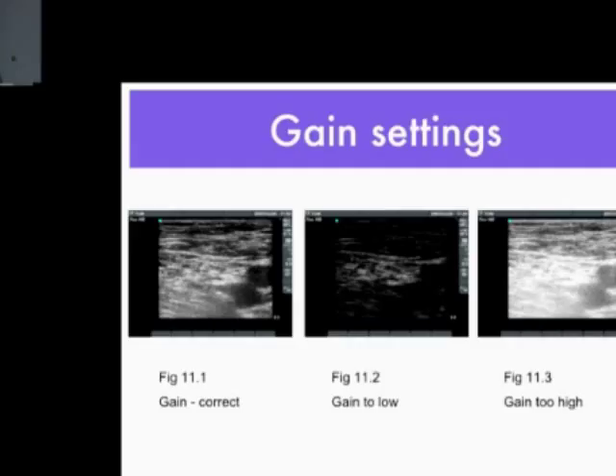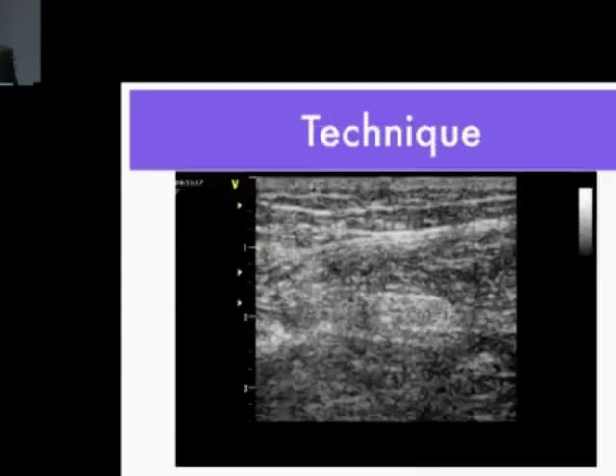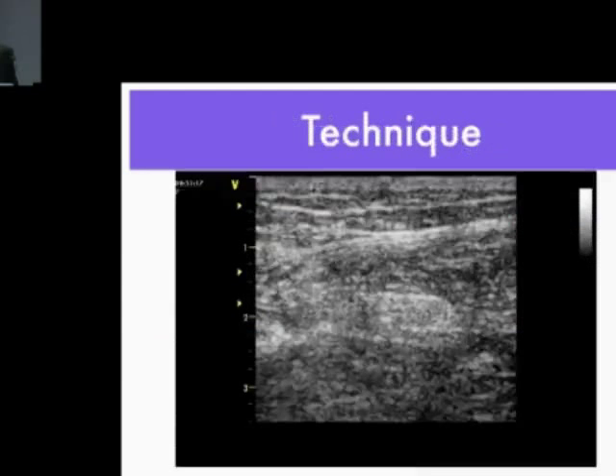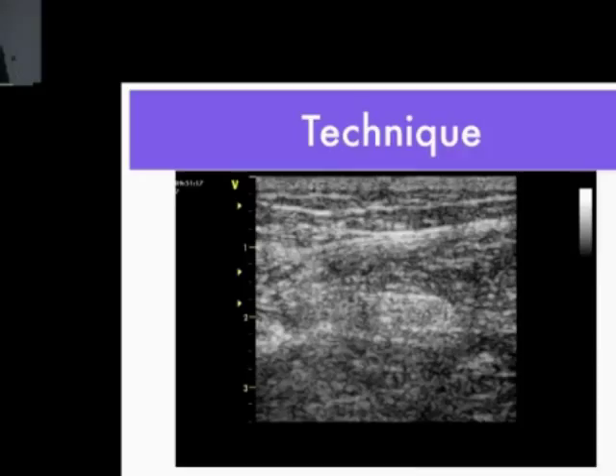Gain has individual preferences, but we must pay attention to it. One of the most important things related to gain is reducing the intensity of ambient light — experienced echocardiographers always reduce ambient light to get less reflection and less tendency to turn the gain up. Some machines have simplified frequency settings such as 'resolution' or 'penetration,' while others allow you to adjust the frequency numerically. Setting the frequency appropriately for the target increases spatial resolution and makes the target clearer.